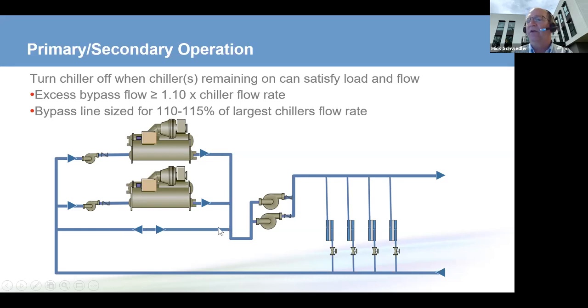So the chilled water is being produced and we have flow in this bypass line. When we get to the point where, when we turn a chiller off and its pump off, we still have excess flow in the bypass line, we know that when we turn it off, we won't have to cycle that chiller back on. And then we probably want to have a little bit of leeway in there, a dead band. So generally, the bypass line is sized to allow 110% of the largest chiller's flow rate, because that's the maximum flow rate that the bypass line should see, because if it goes above that, the sequence of operation for the chiller plant controller should sequence the chiller off. So some designers use 110%, some use 115%.